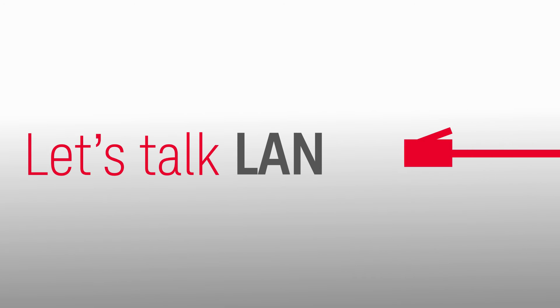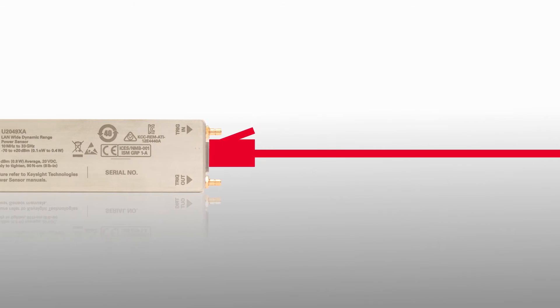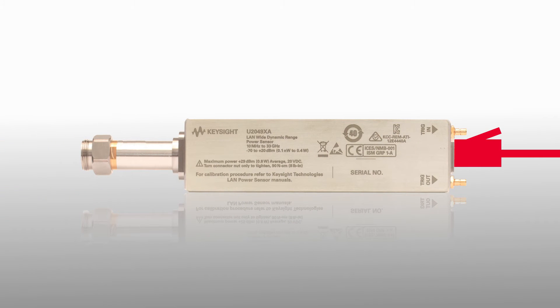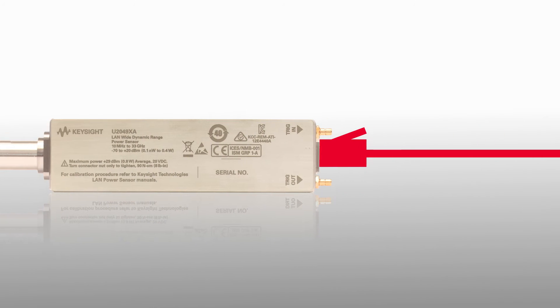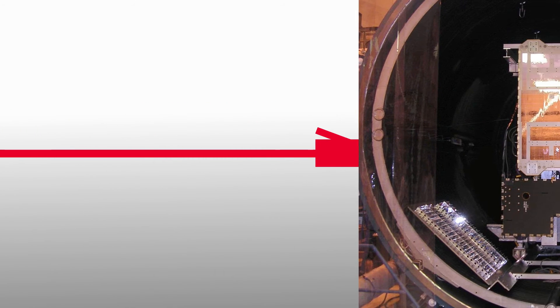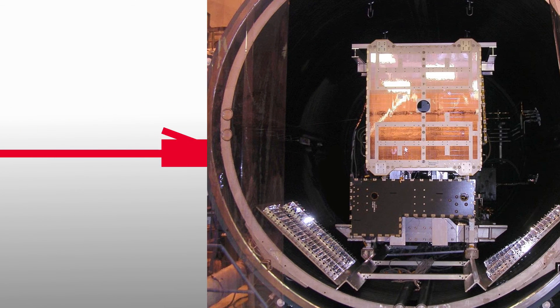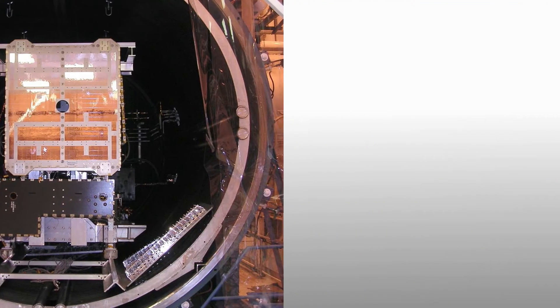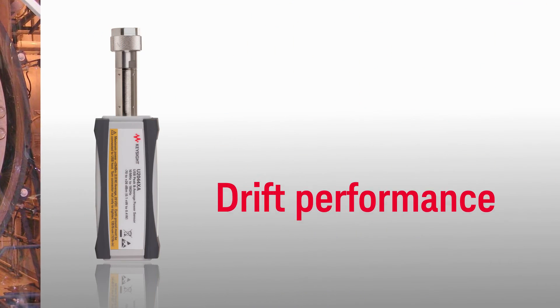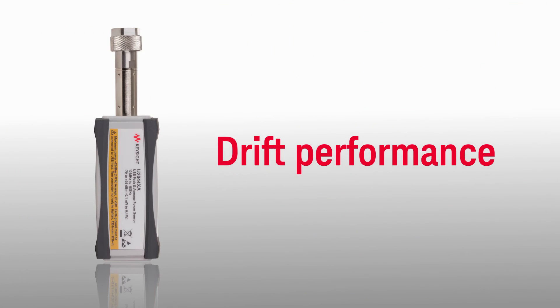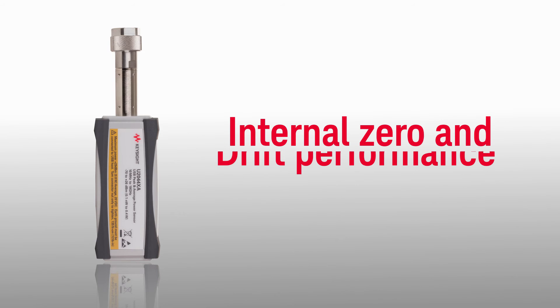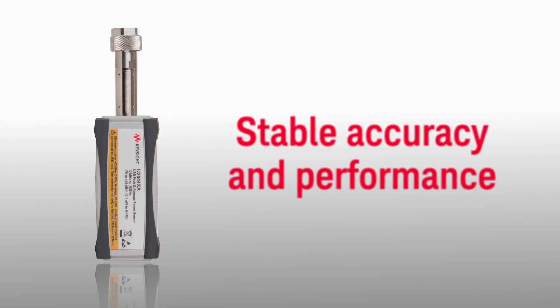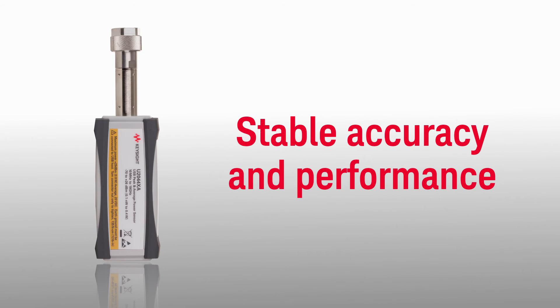Let's talk LAN. Introducing the very first LAN based wide dynamic range power sensor suitable for distances up to 100 meters. Now when you need remote monitoring in harsh conditions such as in a thermal vacuum chamber, you can do it. The sensor provides best-in-class long-term drift performance and internal zero and calibration for stable accuracy and performance.